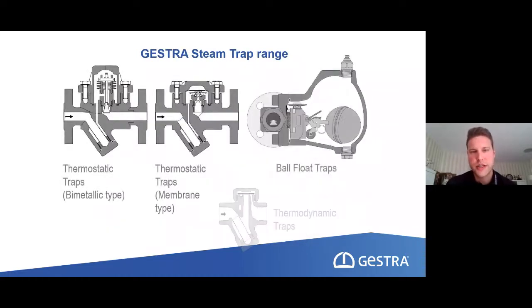So this is our typical steam trap range. You can differentiate them very easily. They even look similar here. You see the two here on the left-hand side. These are so-called thermostatic steam traps. We have a bimetallic steam trap in this part, and a membrane type steam trap, a so-called MK, in this part. These two can be clustered as thermostatic steam traps. We also have a ball float steam trap, which is the most sophisticated one. It has a very good control function and a large body, which gives it a very big capacity, so it can discharge high amounts depending on the design a little bit. We will speak about that one, of course.